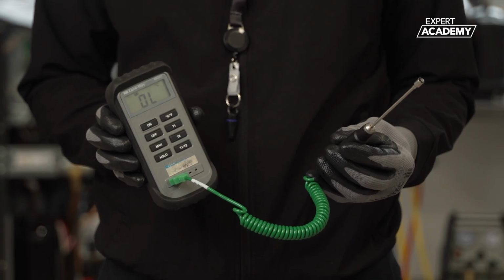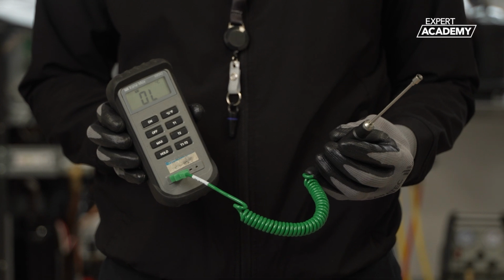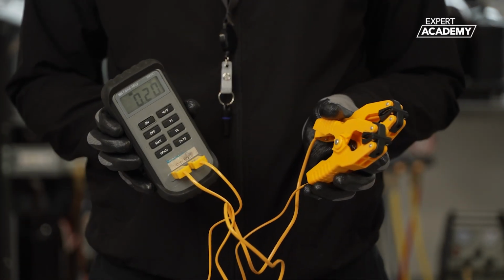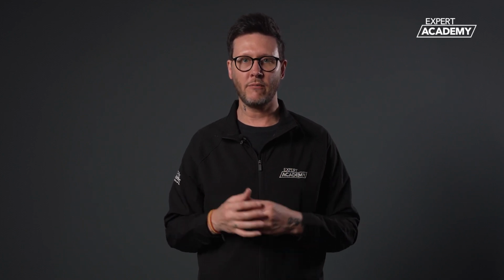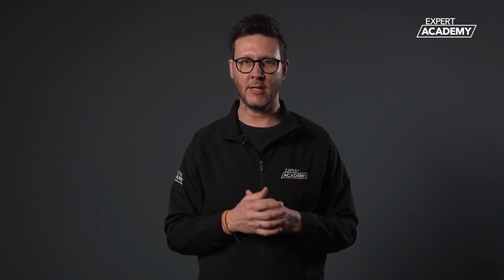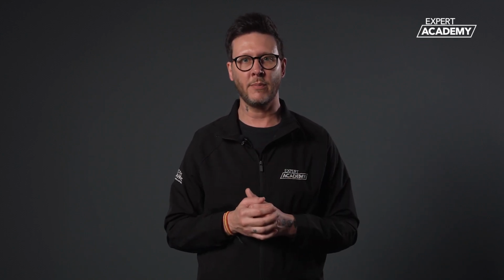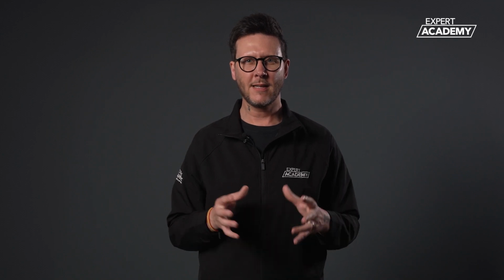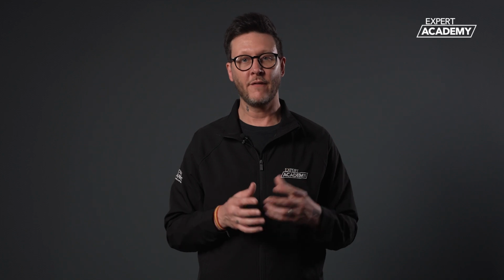Various types of temperature probes and clamps are available, including a single probe to dual clamps. Some gauges have options to connect to apps, enabling you to take single temperature readings or monitor over a period of time. Taking temperatures at different points of the refrigerant circuits can help identify refrigerant issues when used in conjunction with pressure and temperature charts specific to the type of refrigerant being used. These gauges can also be used for other tasks, and many heating engineers may already have them for measuring flow and return temperatures on heating circuits.